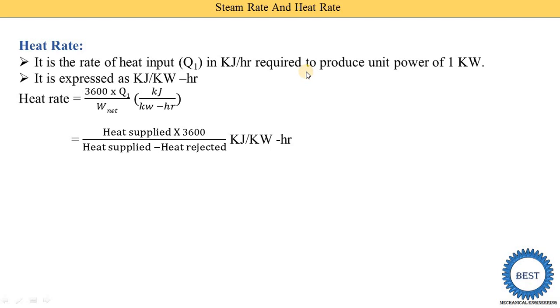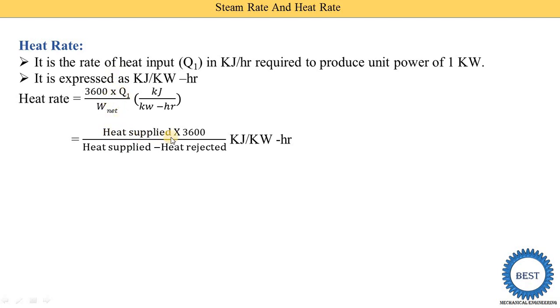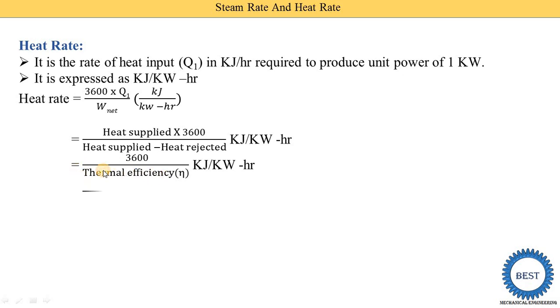Efficiency is equal to net work done divided by heat supply. So heat rate equals 1 upon efficiency. If we supply q1 to the denominator, it becomes W_net upon q1, which is the efficiency. Therefore, heat rate equals 1 upon efficiency. Further simplifying: q1 is the heat supply, and W_net equals heat supply minus heat rejected. So heat rate equals 3600 divided by thermal efficiency. This is the second equation of heat rate.